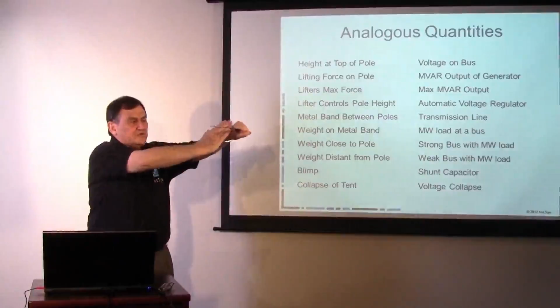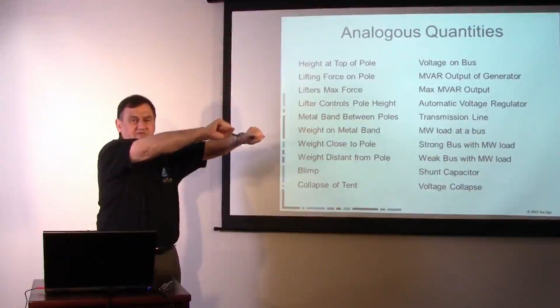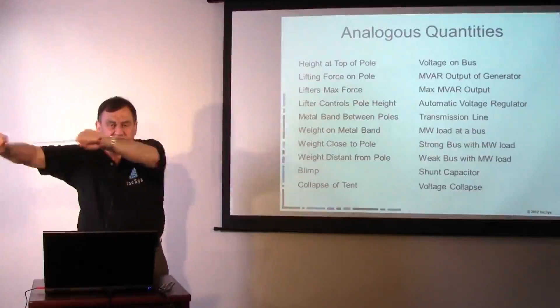In fact, the maximum power you can move across this line is a function of the angle. If you have voltage regulation at both ends, you can move that line to 90 degrees. And then you can have another line and another line, okay? Each running at 90 degrees. But as soon as you lose the voltage regulation at a midpoint, you will get voltage instability, because instead of having 90 degrees between here and here and 90 between here and here, you're going to end up with 180 between here and here, and that will cause voltage collapse. So just the mere fact that that generator takes its AVR off of voltage regulation can give you instant voltage collapse. So it's an extremely important thing to stay in sync with your power plant operators and have them alert you if for some reason that unit's going to hit that limit or it's going to take the voltage regulation off of control.